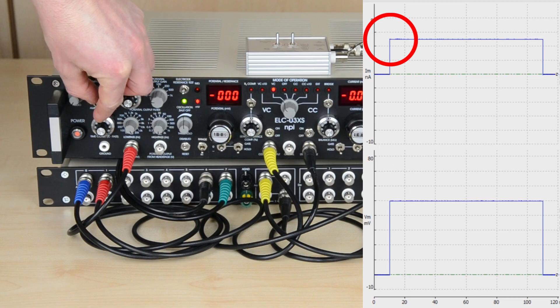Now switch the model cell to cell 1 with 50 megohm. According to Ohm's law, with a 50 megohm cell and a 50 mV pulse, we should expect a current of 1 nanoampere. However, we only have about 0.8 nanoampere. The reason is the series resistance, in this case the additional resistance from the 10 megohm electrode.